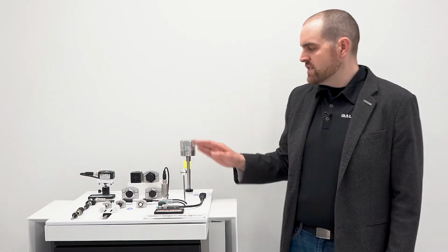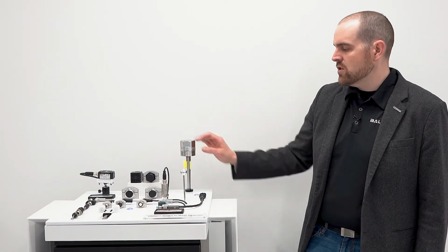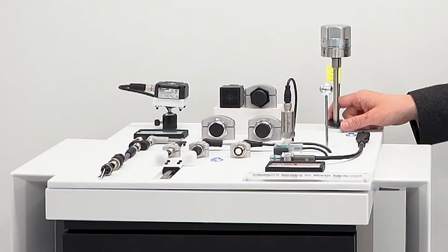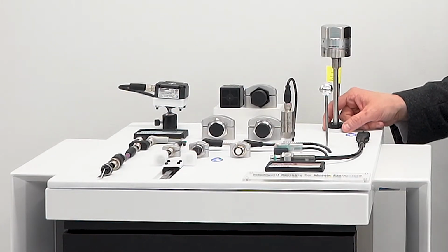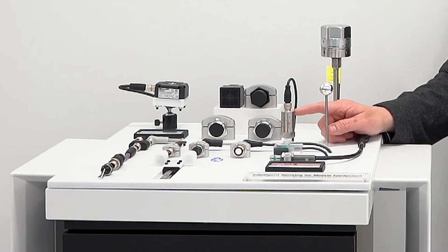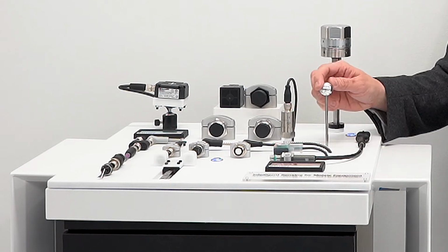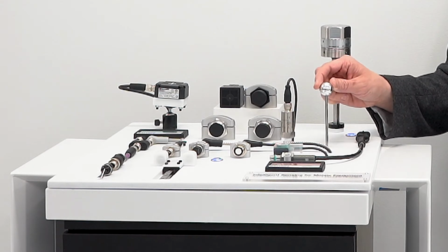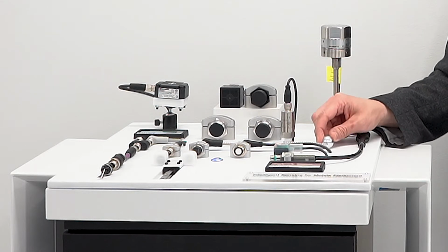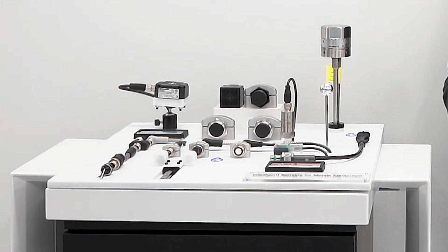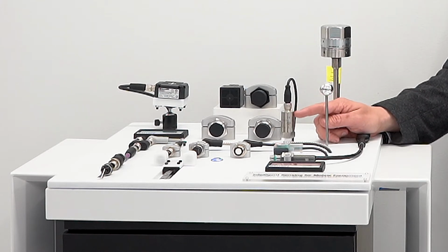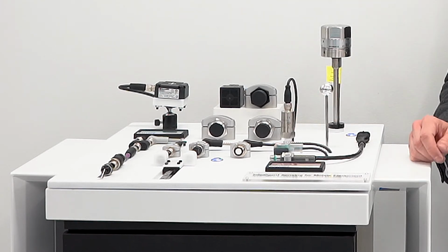The fifth application I'm going to talk about is hydraulic system monitoring. Here you can see the linear position transducer again. We can use this with a float to detect how much oil is in the hydraulic power unit storage tank. We have pressure transducers that give us the amount of pressure available. Some people use that on a cylinder to detect position based on pressure, but you can also use the pressure just for system monitoring itself.